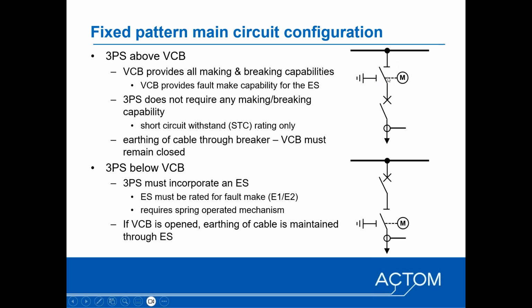And I'm referring to the position of the 3-position switch relative to the circuit breaker. So in fixed pattern switchgear, you have the 3-position switch, which includes the disconnector and earthing switch, and provides the isolation requirements necessary in terms of the standard, and then the circuit breaker for the making and breaking performance. So when the 3-position switch is located above, all the switching and making and breaking capabilities are fulfilled by the circuit breaker. The 3-position disconnector is simply a 3-position switch and does not require any making or breaking capabilities, and is therefore an economical solution, and effectively just provides the 3 different positions.